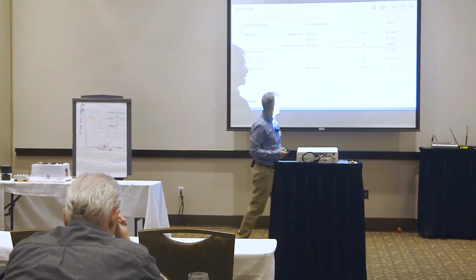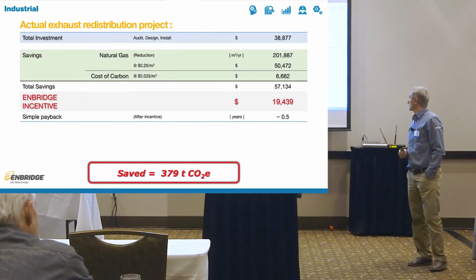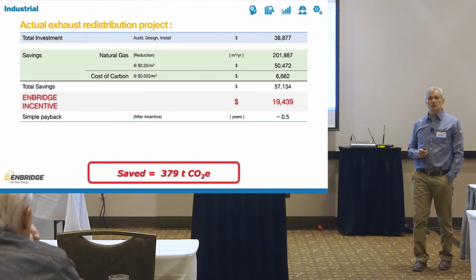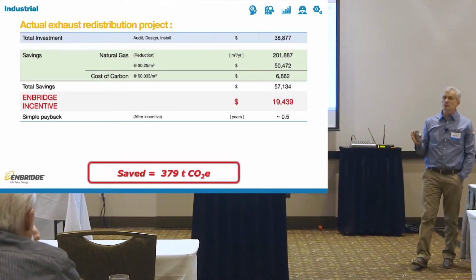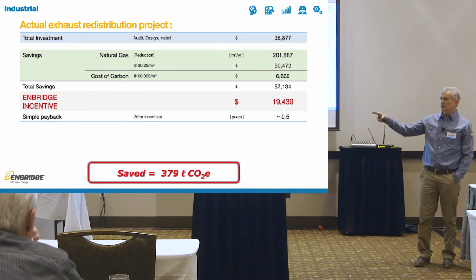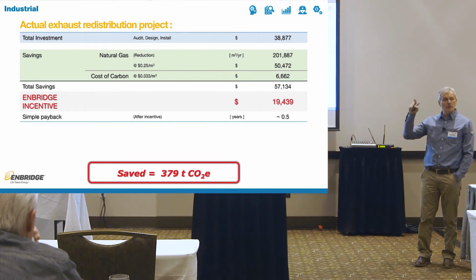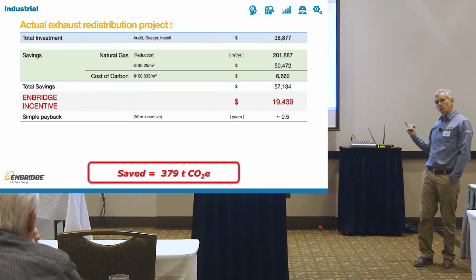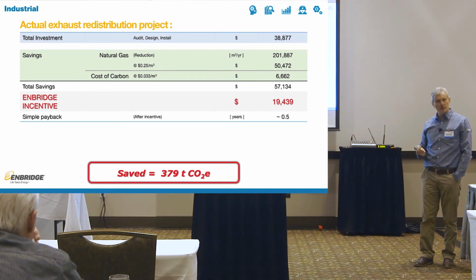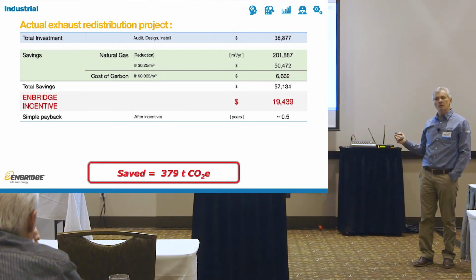They saved 201,000 cubic meters of natural gas for $57,000, $60,000 worth of savings, and we gave them $20,000 worth of incentive. Nothing else was required. It's a switch that turns these fans off in the wintertime, turns on the fans in the air socks, and 3 air socks that go around their roof. Since then, they actually installed 2 more air socks to recover even more heat. They've never been as warm in the wintertime as they were last winter.